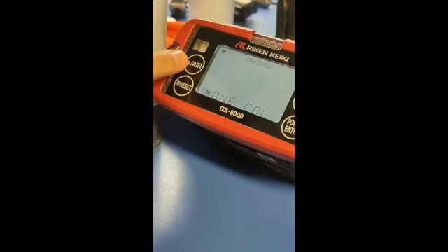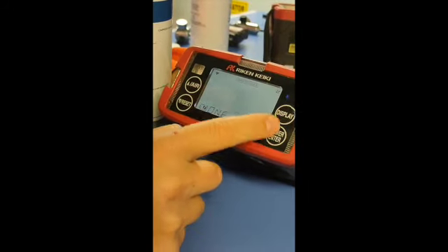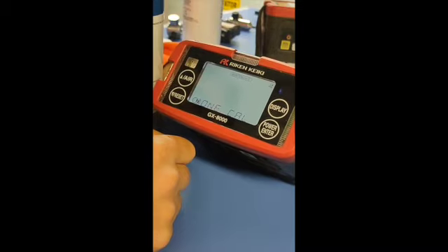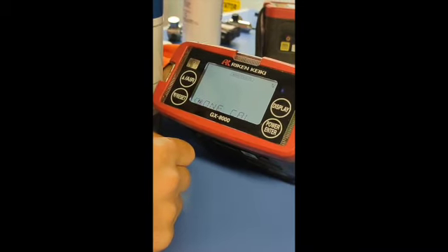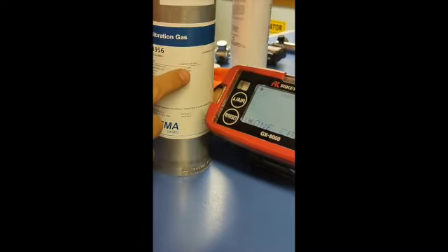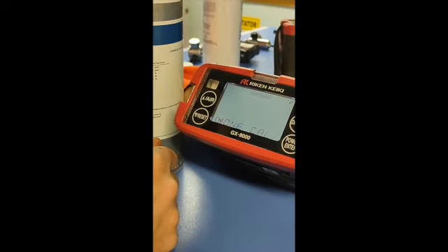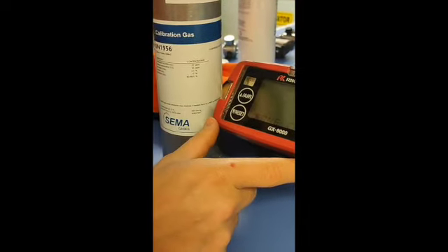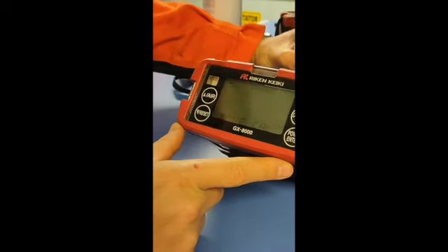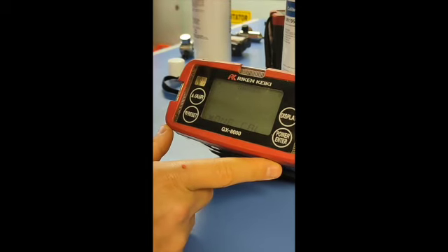In one cal mode, we test only 4 sensors. We span gas test. So we give the sensors a calibrated value from the bottle to be double checked by the portable gas detector. So what about the 5th one, the hydrocarbon percentage per volume? That one I need to give also a known value.